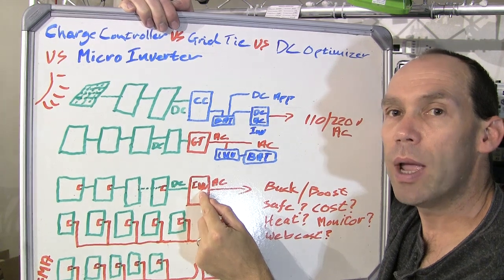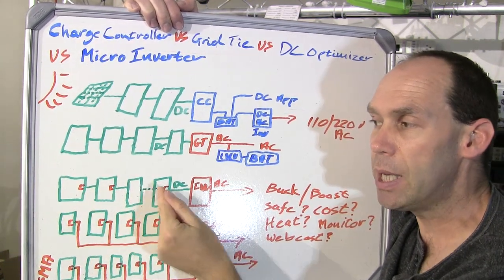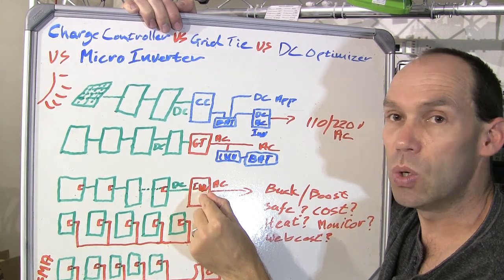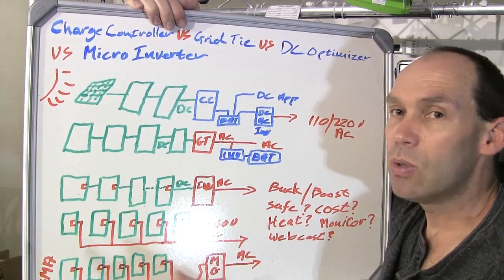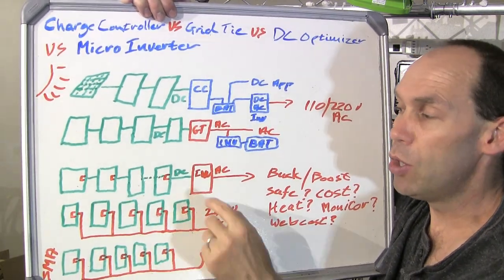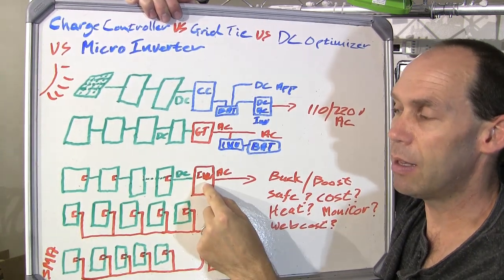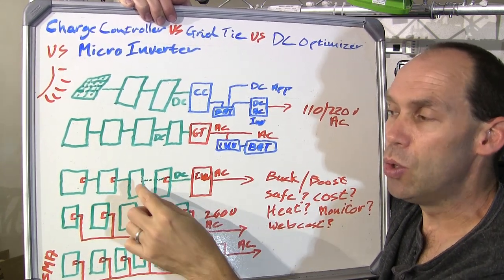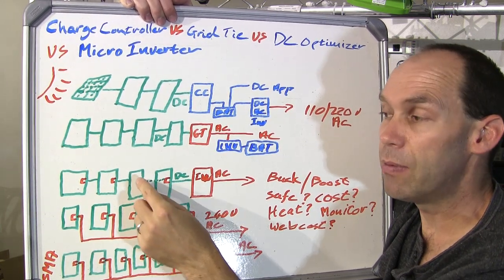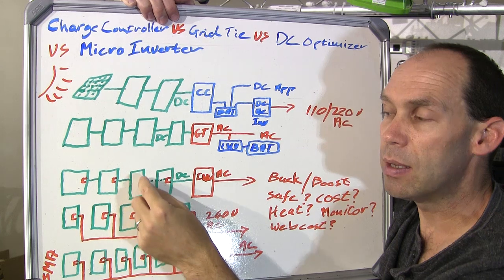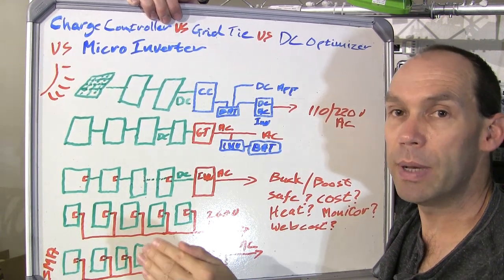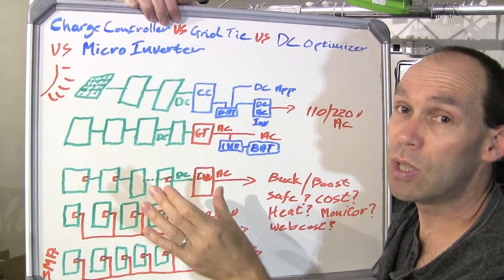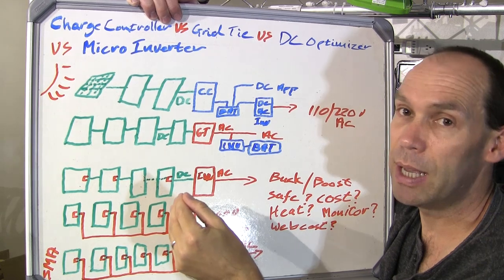The other types of technologies where more specialized MPPT is done at each panel require an inverter with a single voltage input, because the MPPT work is being done at the actual panels — they bring DC in at a specific voltage level to a single point. Therein lie some of the challenges: when you have these single points, if that fails, everything goes down. However, some of these systems do have ways of routing around a failed panel or optimizer. Some systems employ special gateways which communicate with the optimizers to see what's going on, adjust their performance, and eliminate faulty units from the system.